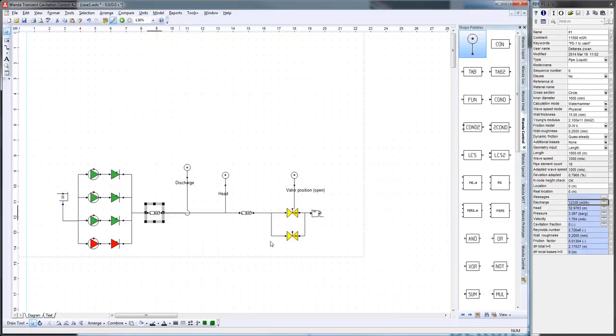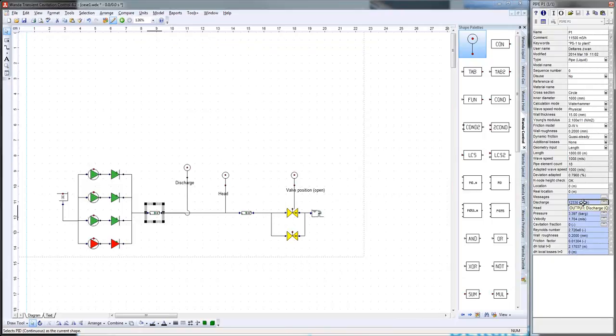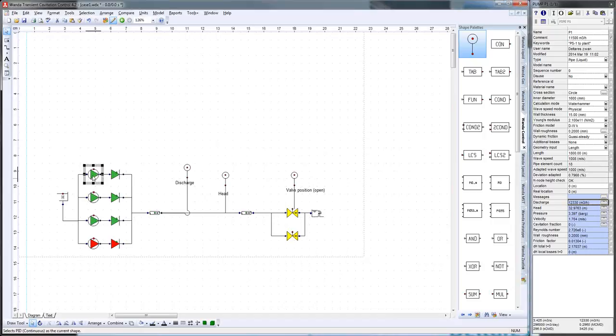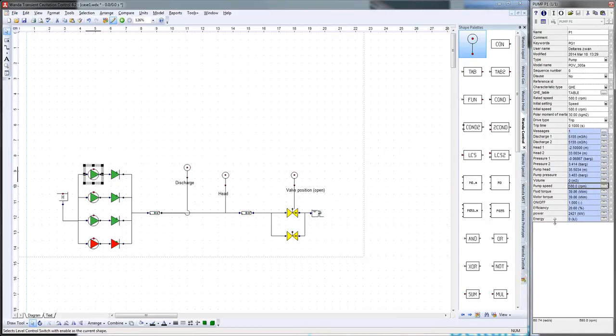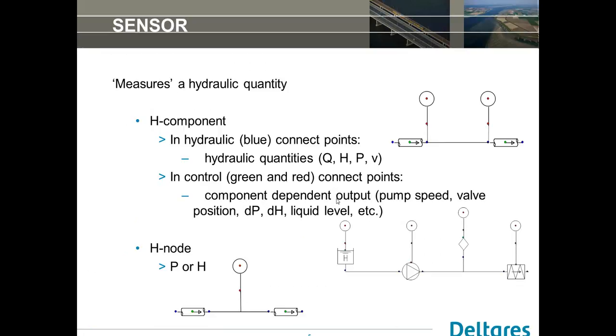Another trick which might be useful is to put the information button here in the selection property window. If you then select the quantity, you can see down here this value in the different units which are available, and you can see also the SI units given first. Items where this becomes more important are, for example, the valve position, which is not 0 to 100%, but it's 0 to 1. And also the pump speed, which we normally use in RPM, but the SI unit is radians per second - so 580 RPM corresponds to 60.74 radians per second.